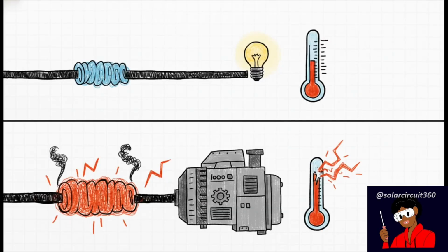And we've got to remember that power loss formula we talked about earlier. Doubling the current causes 4 times the heating loss. That means a connection that seems totally fine when you're just running, say, a couple of LED lights, can rapidly become a major power drain and a really serious fire risk when you kick on a heavy load like a microwave or a water pump. The heat loss multiplies exponentially, and that heat is literally your missing voltage burning away into the air.